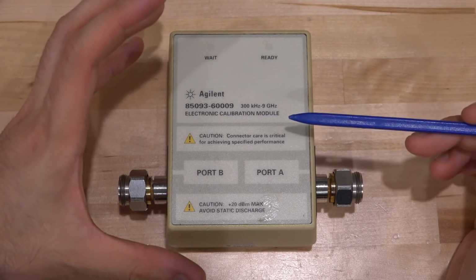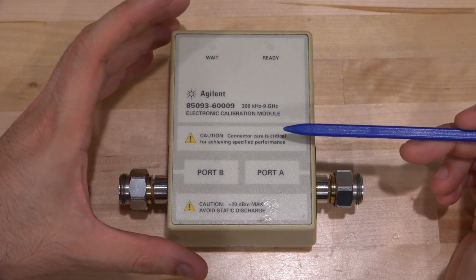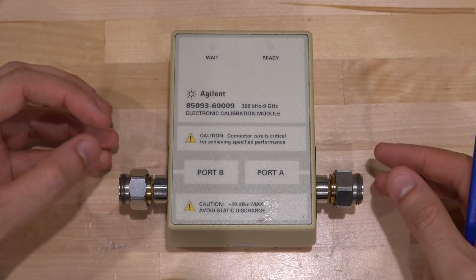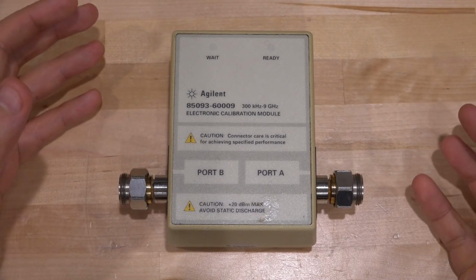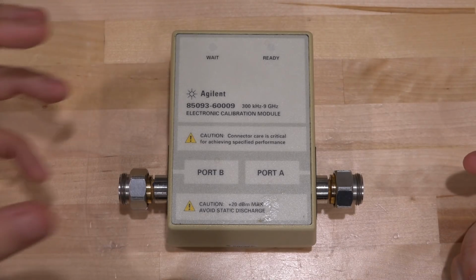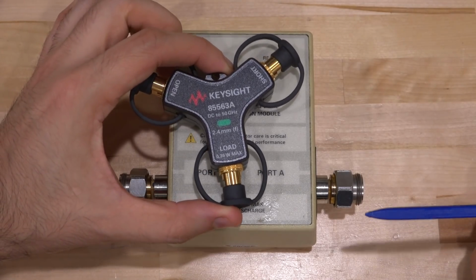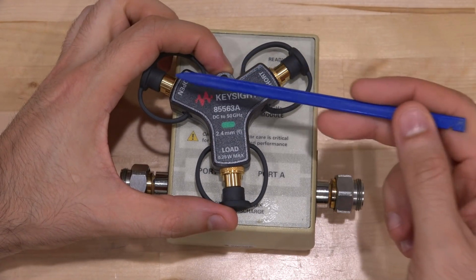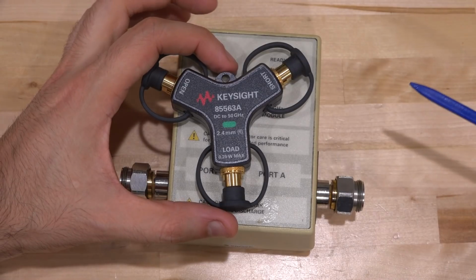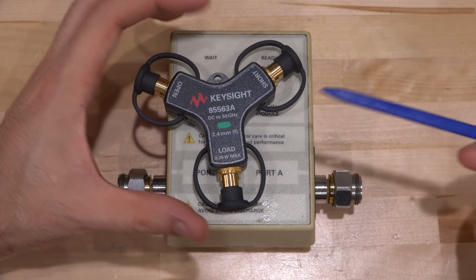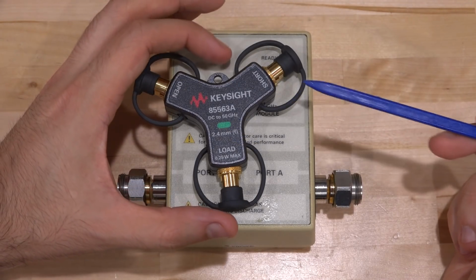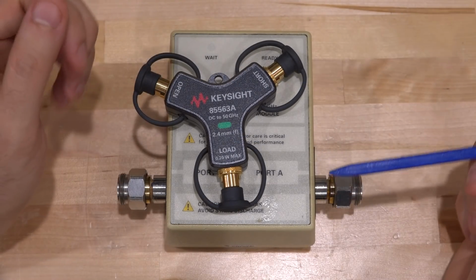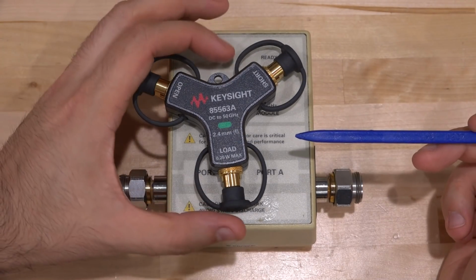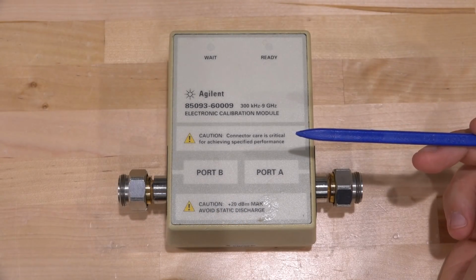Now, the major advantage of having an electronic calibration module is you only make one connection. So you connect this to your network analyzer and that's it. You don't have to connect and disconnect to jump between the different standards. For something like this, you're going to have to connect each port to each of these separately, do the calibration, do it again on the other port, and so on and on. And that not only wears out your cable, but it also takes a long time and it moves things around. And it's going to be very difficult to perform metrology grade calibration.